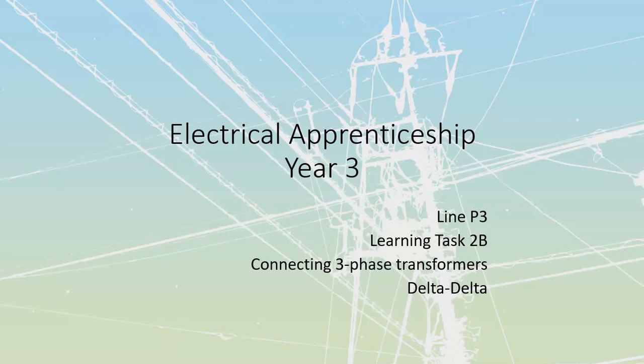We have places where we especially like to use delta, particularly in medium voltage ranges and when dealing with balanced three-phase loads that don't need a neutral. So, three-phase electric heat in industrial processes, or motors in industrial processes, or sometimes even sub-distribution, just to knock it down to a safer level and then drop it down further.